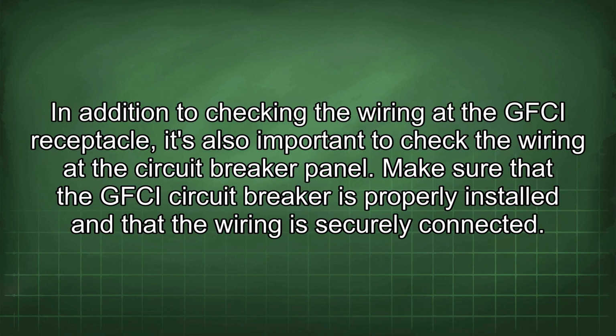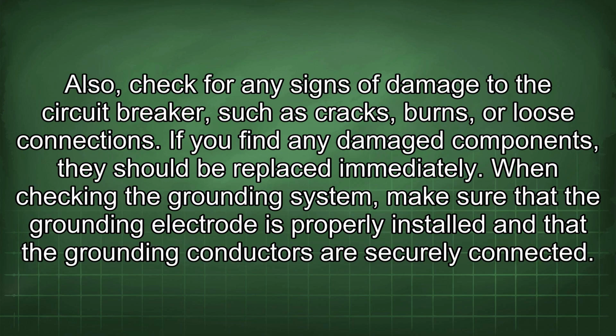In addition to checking the wiring at the GFCI receptacle, it's also important to check the wiring at the circuit breaker panel. Make sure that the GFCI circuit breaker is properly installed and that the wiring is securely connected. Also, check for any signs of damage to the circuit breaker, such as cracks, burns, or loose connections. If you find any damaged components, they should be replaced immediately.